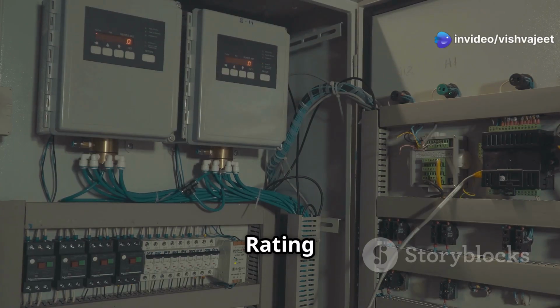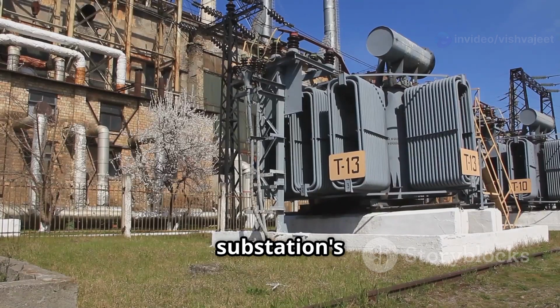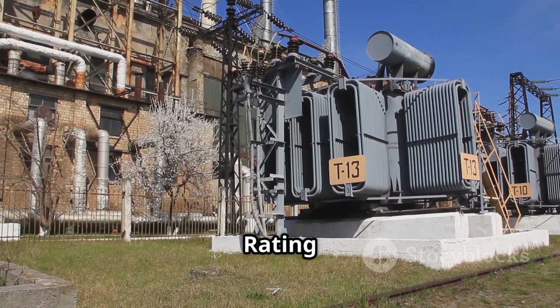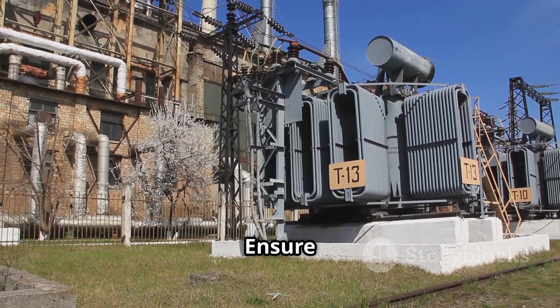Voltage rating: match the transformer's primary and secondary voltage ratings to the substation's requirements. Power rating, MVA: ensure the transformer can handle the maximum load demand.